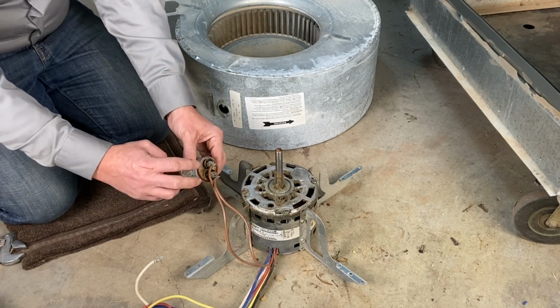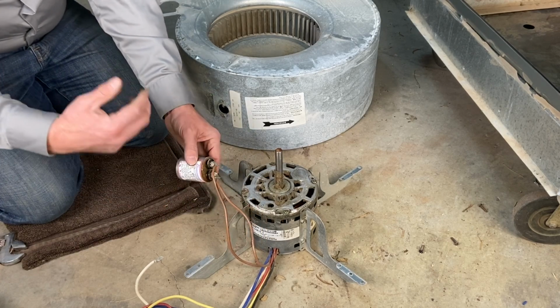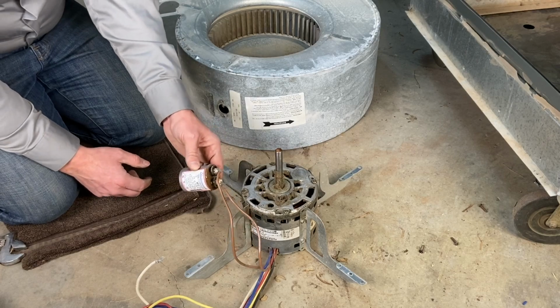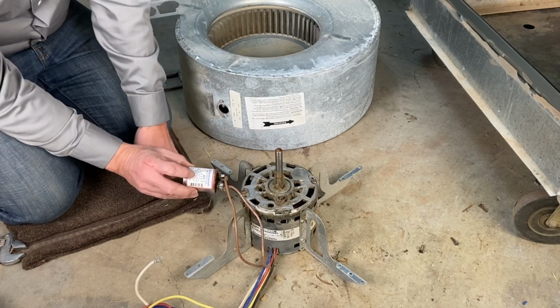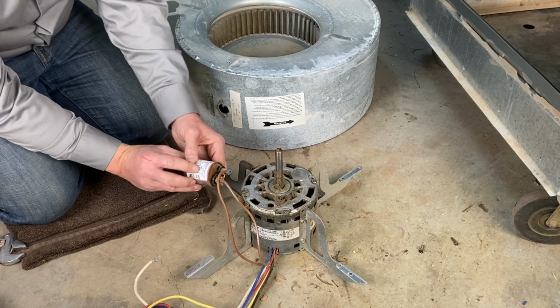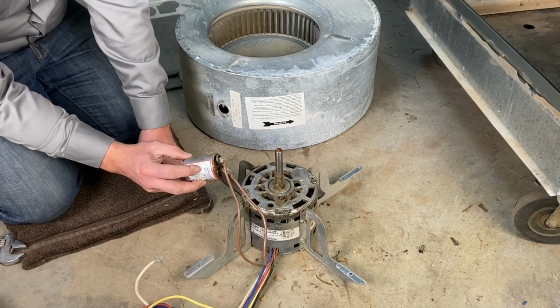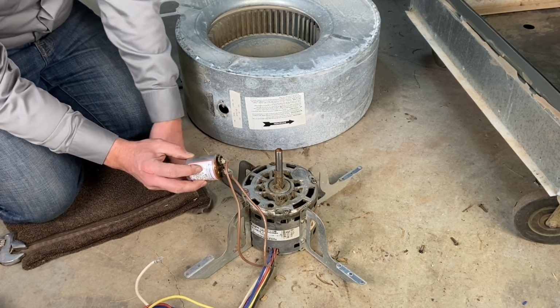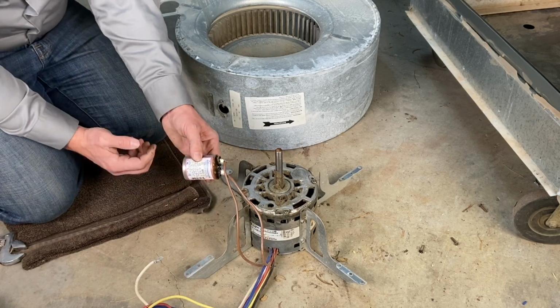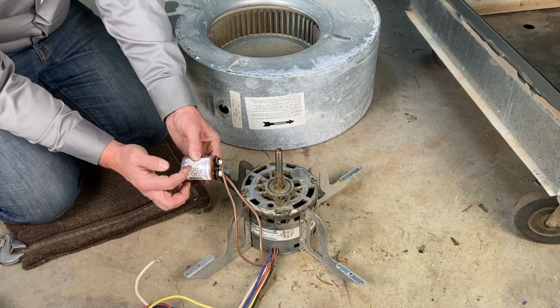Hook my meter on microfarads and hold it firmly on one side and the other and see if that reading matches it. If it doesn't, if it's out of range, we'd want to replace this. This has a plus or minus of 10%. So it could be 10% higher than 7.5 or 10% lower. Notice I said percentage and not microfarads. So if we do the math, you can calculate it.